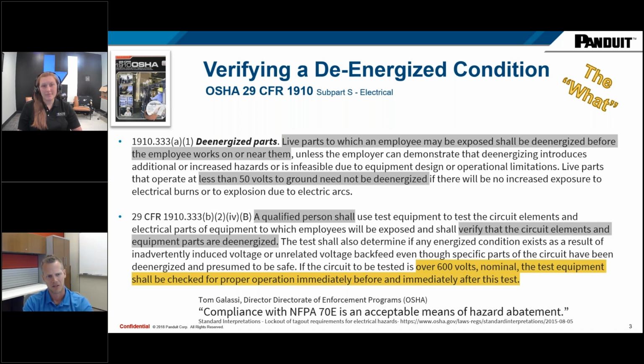So the tie between OSHA and 70E really is that 70E was created at the request of OSHA, and OSHA supports its use, as you see my little quote down there at the bottom. Tom Galassi, he's retired now, but a former director, in one of his standard interpretations, which I've got linked there if you wanted to check it out, states that compliance with NFPA 70E is an acceptable means of hazard abatement. So 70E, while it's not a regulation, if it is being followed, it is a means to accomplish OSHA compliance, which is a great point to have, right? You don't have to use 70E, but it's worth using it unless you want to come up with your own processes, which is a whole different level of effort.